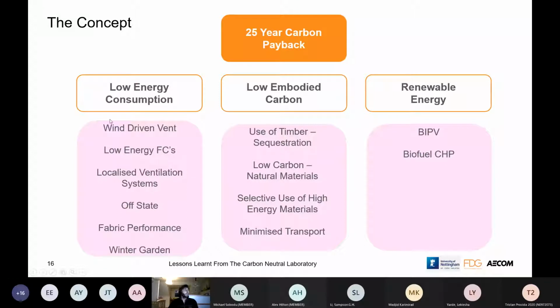We couldn't use natural ventilation in the original concept because of the requirement for more intense chemistry. So we use the wind to help drive the ventilation, but it's still mechanical in most areas. We have low energy fume cupboards, and importantly, we localize ventilation systems. Rather than have big AHUs centrally, we put them local to the area they're serving, so they provide exactly the right airflow at exactly the right temperatures, rather than having big central systems that are very inefficient.